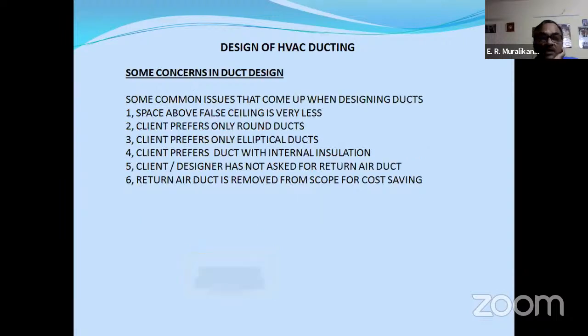Now, some concerns in duct design. Some common issues come up when designing ducts. The space above the false ceiling is very small because the architect has already decided this much space I'll give you, and you have to put the duct in it, so we do whatever is possible. The client prefers only round ducts, fine. Some prefer only elliptical, fine. Some want internal insulation. Then the client's design is not for a return duct. People ask why put the money on a return duct. So the return duct is removed from scope for cost saving. Earlier it was in the tender, and it was later deleted just for cost saving. These are the concerns in ducting design.